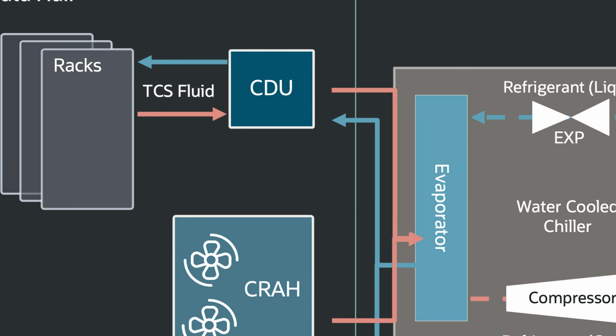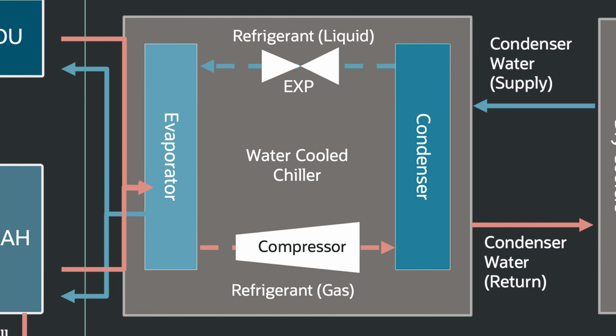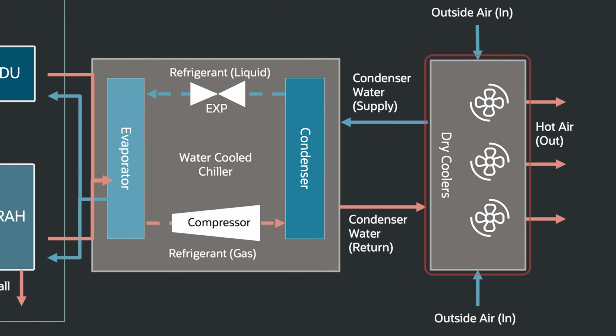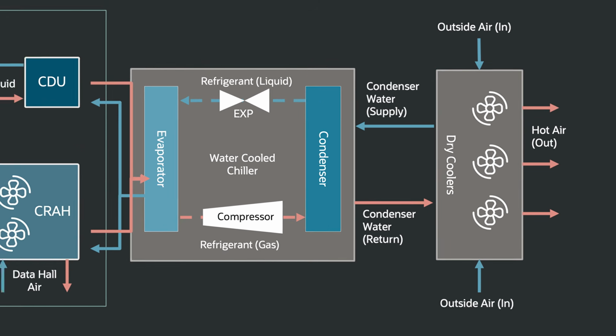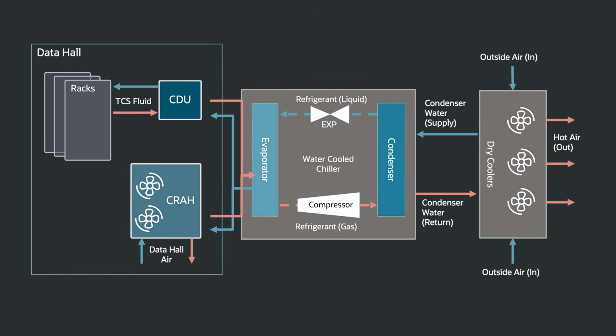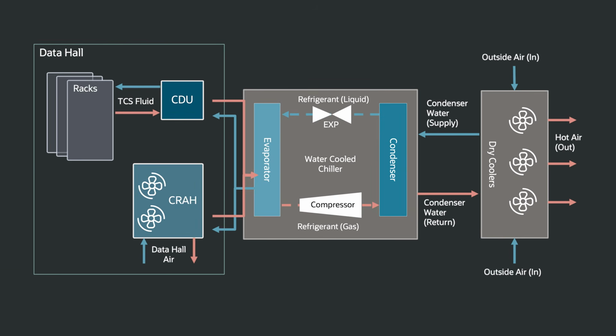And then there is a water-cooled chiller. It's also a closed loop. Then there is another dry cooler. That's the one for rejecting the heat. Our design goal is zero net water consumption. Both the TCS loop and the facility water loop, or the external chilled water loop, are 100% closed loops. Additionally, heat captured is ultimately rejected via the dry coolers. So there are no evaporative coolers. There is no chiller water usage in our data centers.